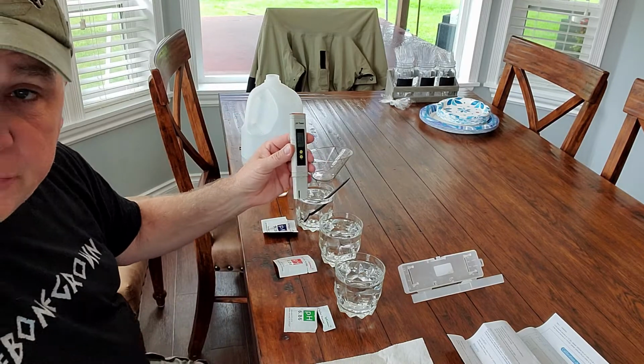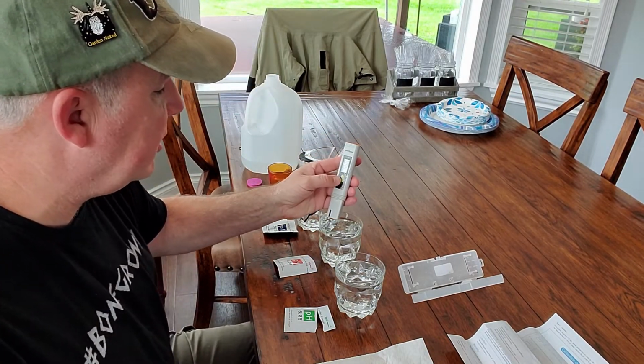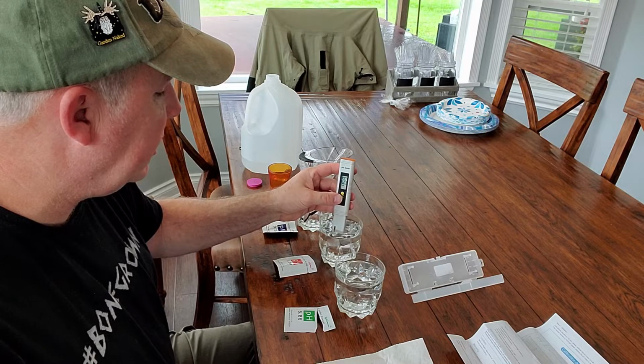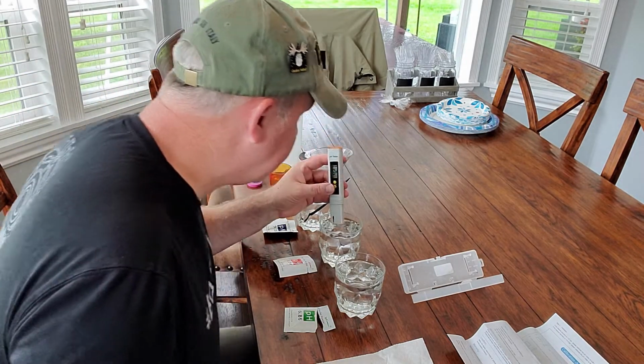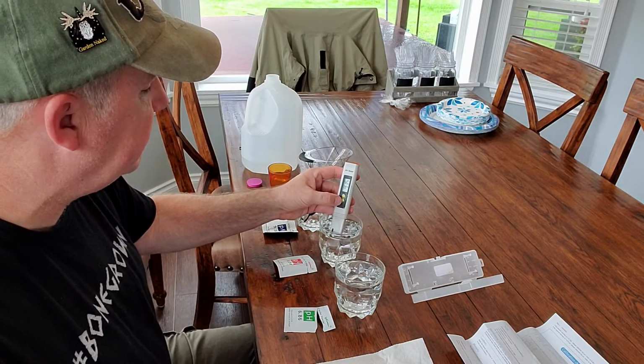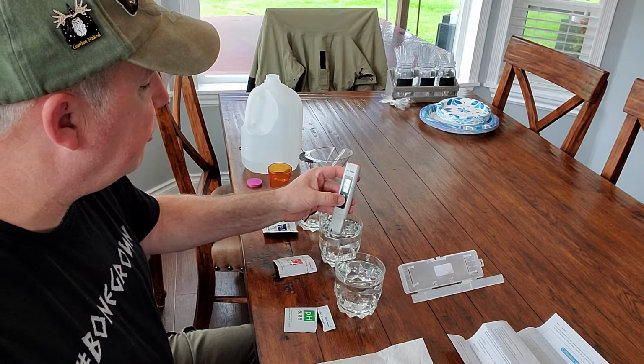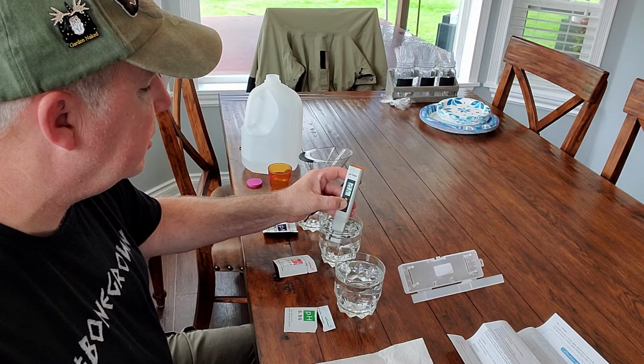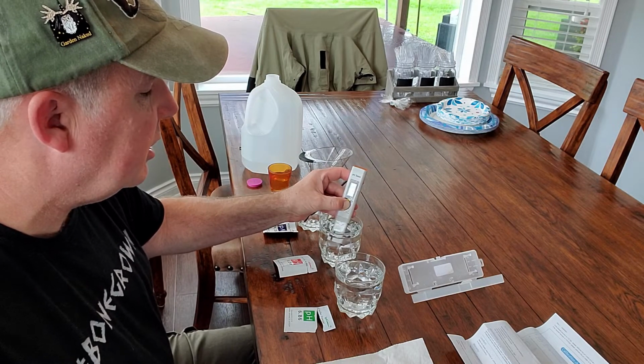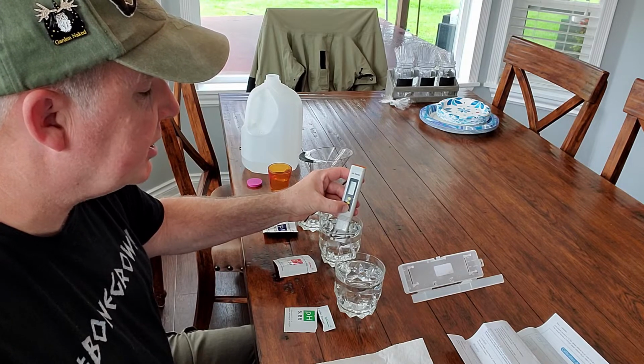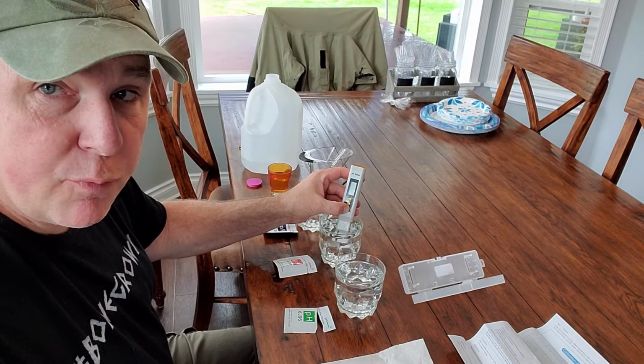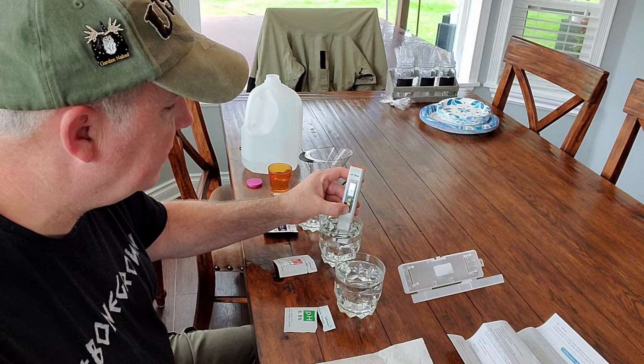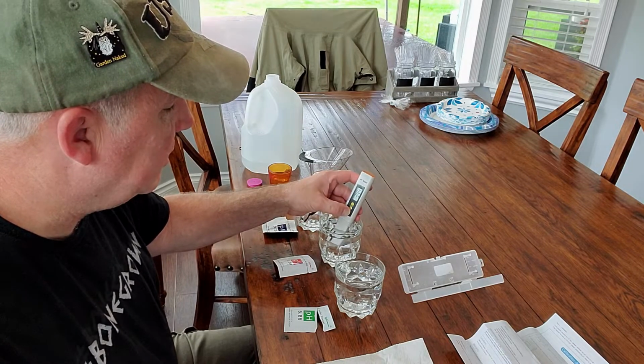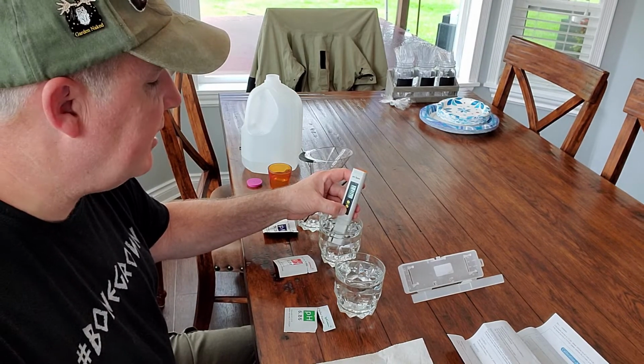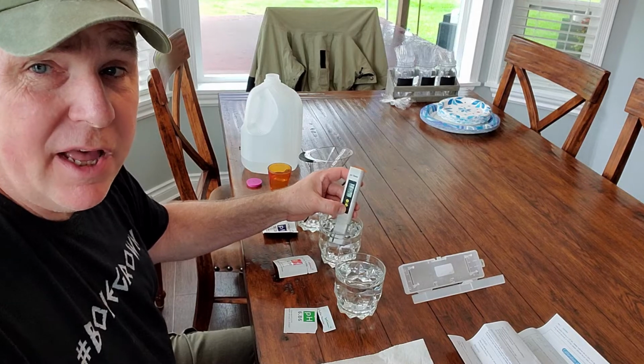This solution is made with 250 milliliters. I'm going to put it in, make sure that everything's stirred up and there's nothing on the bottom, and I'm going to press and hold. I release it, and it's holding, flashing at 4.00. Now it's calibrated at 4.01. That's what I'm looking for.